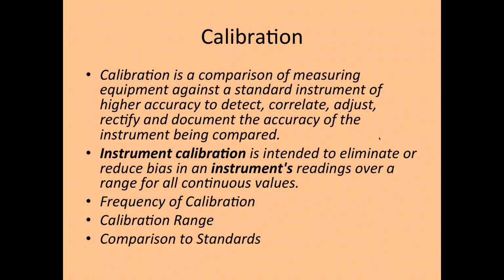That calibration needs to be documented on the machine. There needs to be a little sticker on the machine that says that it was calibrated, was found to be within the calibration range, that it followed a certain standard, and when the next calibration is due. And that usually falls, I put all of that underneath my quality director so that she would be able to make sure that we had good control on our quality.